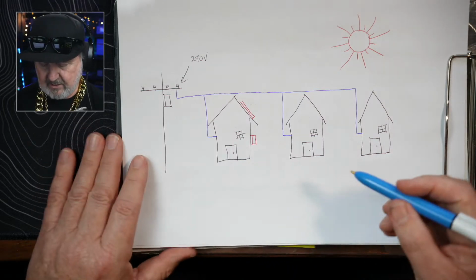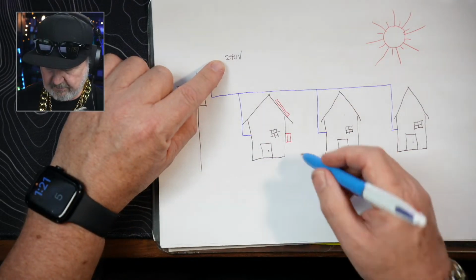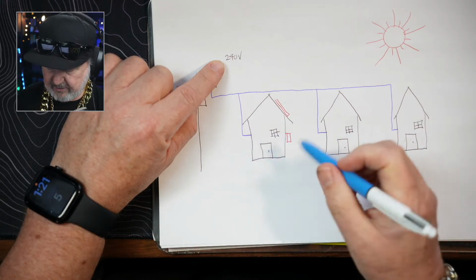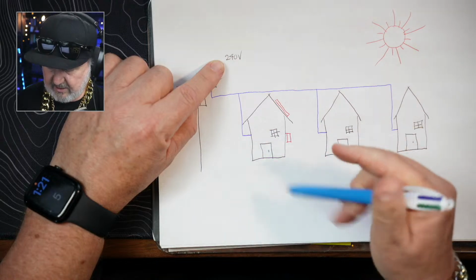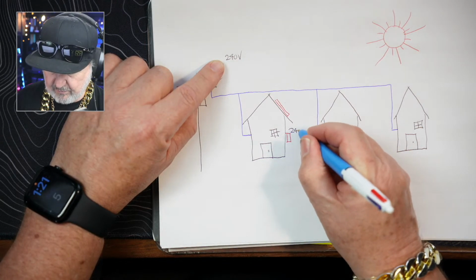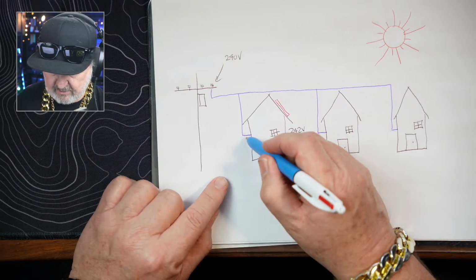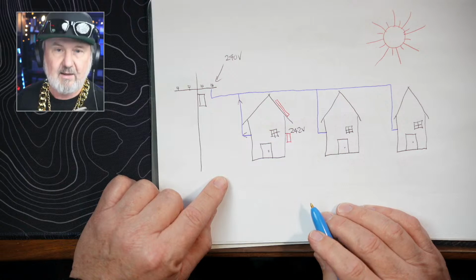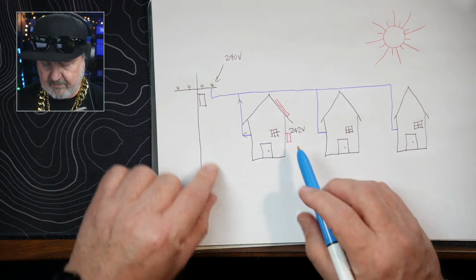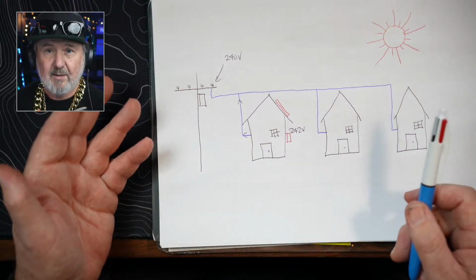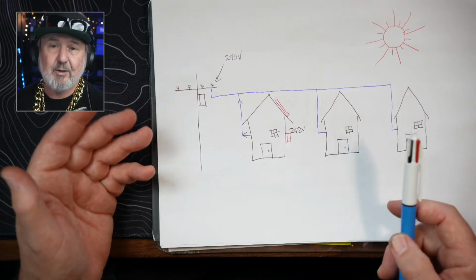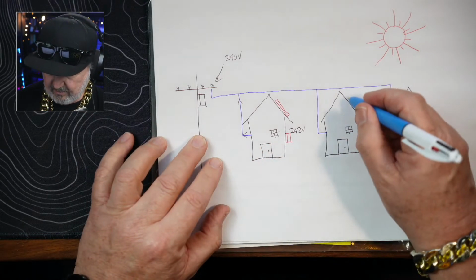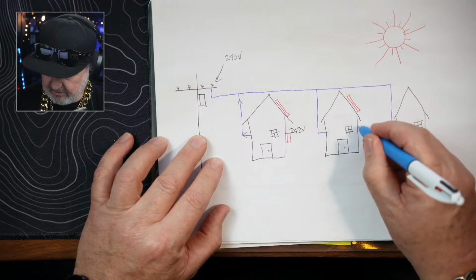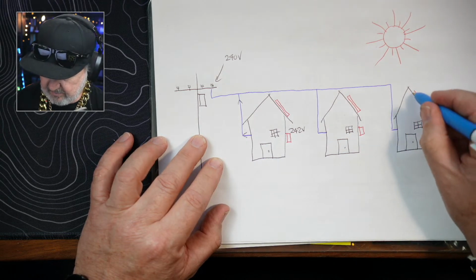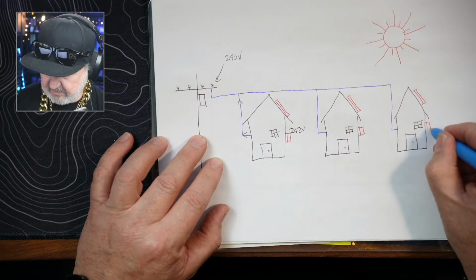Okay, so going back to this little drawing here, we might have started at 240 here, but at the inverter, to pump power out, we're actually going to be higher. So we might be at 242 volts here, and that means power will now flow in this direction towards the grid. But then you've got no problems. 242 is still within the limits for New Zealand for 100% power generation. But then your neighbour sees that you've got solar and thinks it's a great idea. And they put on solar and their neighbour puts on solar and they're all on the same phase.